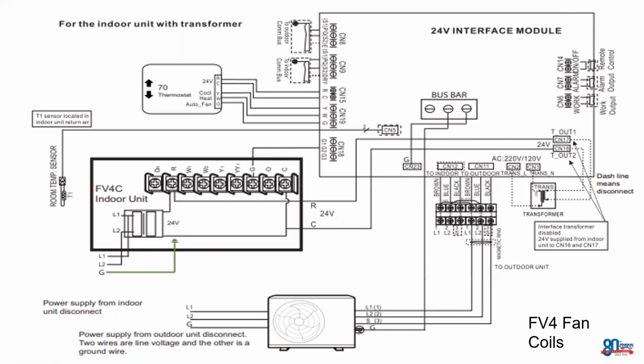Okay, so we have our power coming from our outdoor unit, feeding up and powering our 24-volt interface to give it line voltage power, and also so that it can talk to the outdoor unit and display applicable codes, and also tell the outdoor unit, depending on what that indoor unit needs, whether it be a cooling call, a heating call, or a call for the fan.